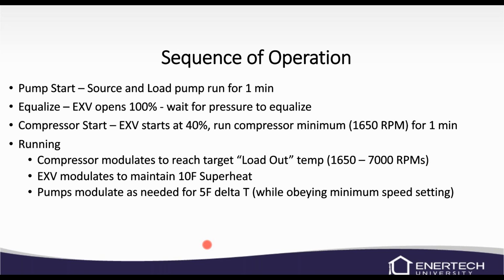Next, it's going to equalize, so the expansion valve is going to open and wait and make sure that the pressures are equalized. Next, the electronic expansion valve is going to be about 40% open, and then the compressor is going to run at about 1,650 RPMs, or minimum speed, for about a minute.